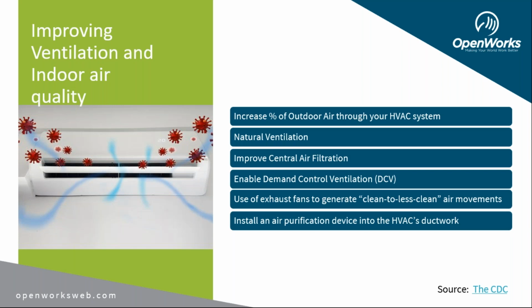Our next strategy is generating clean to less clean air movements. This is done by reevaluating the positioning of supply and exhaust air diffusers or dampers and adjusting zone supply and exhaust flow rates to establish a measurable pressure difference.